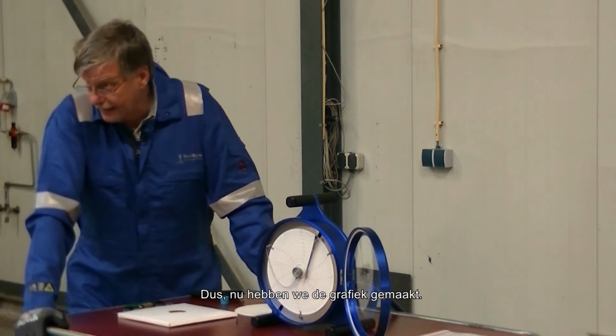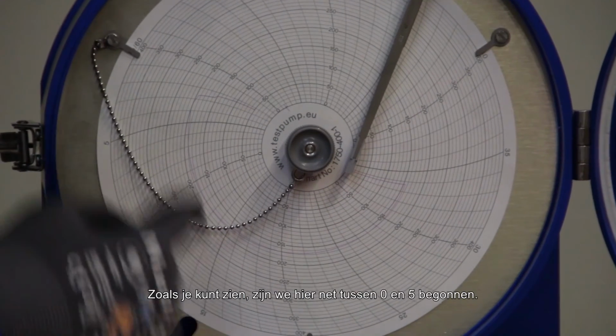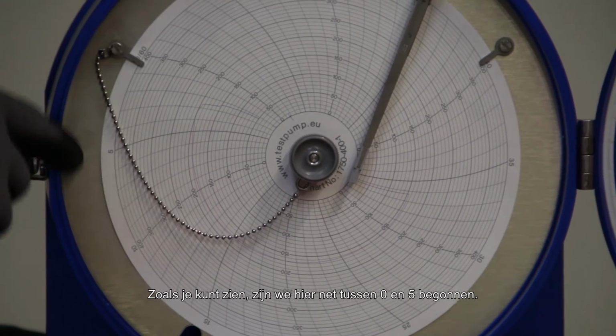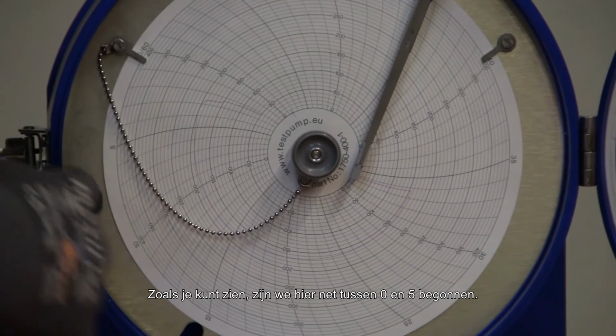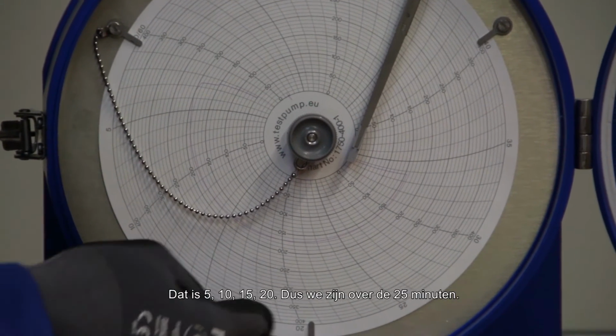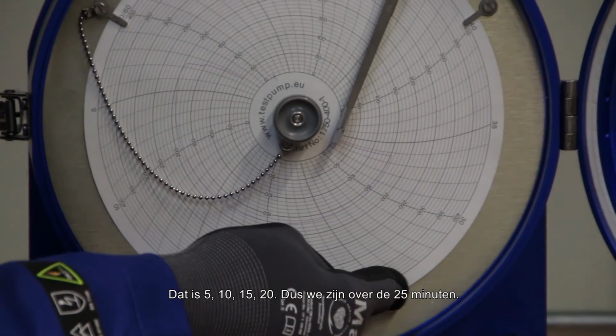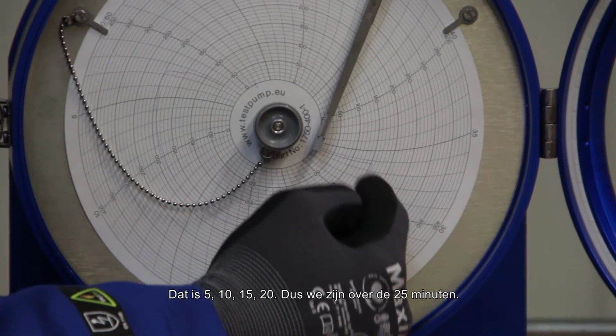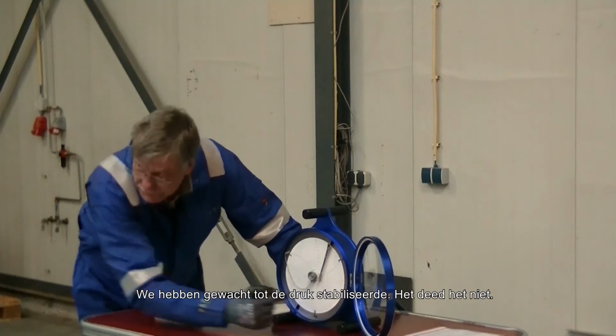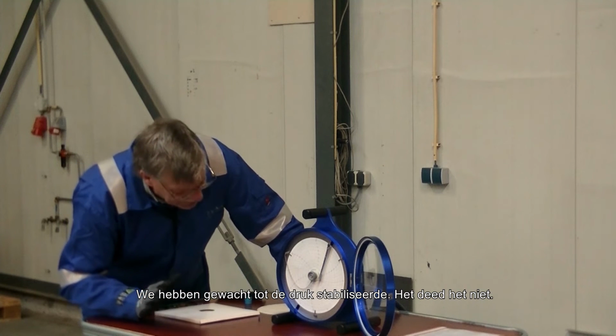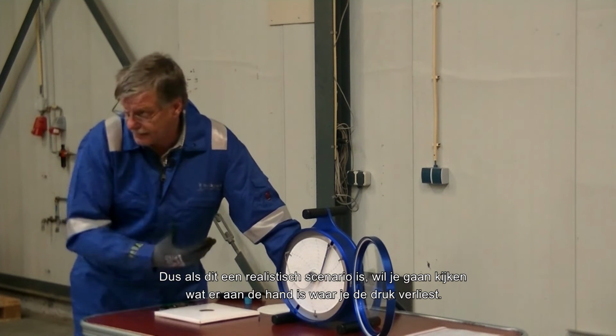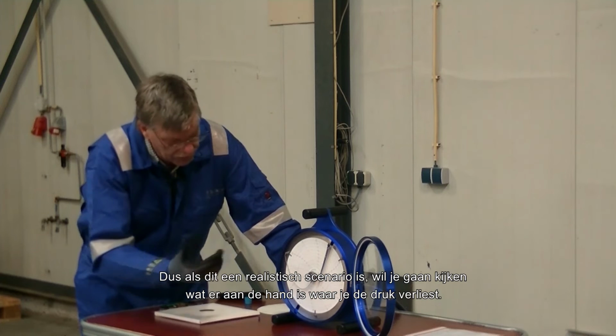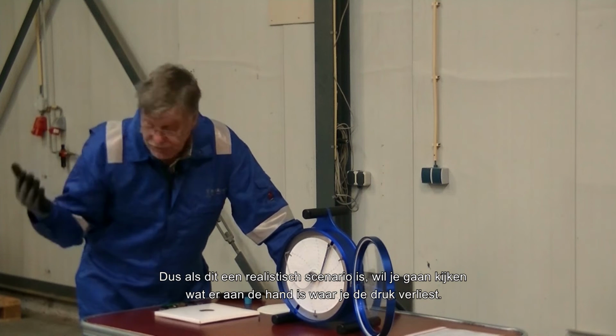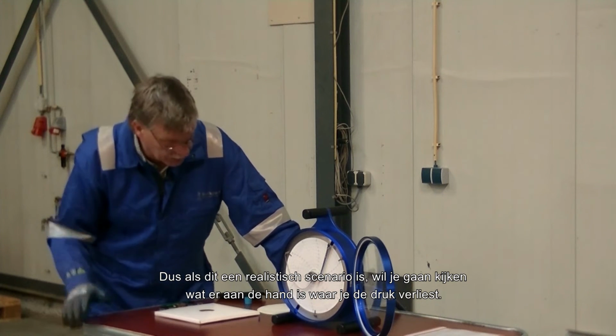So now we've created the chart. As you can see, we started here just between 0 and 5. That's 5, 10, 15, 20. So we're over 25 minutes. We've waited for the pressure to stabilize. It didn't. So if this is a real life scenario, you want to go out there and have a look what's going on, where you're losing the pressure.